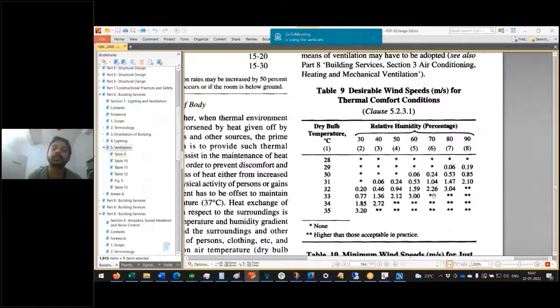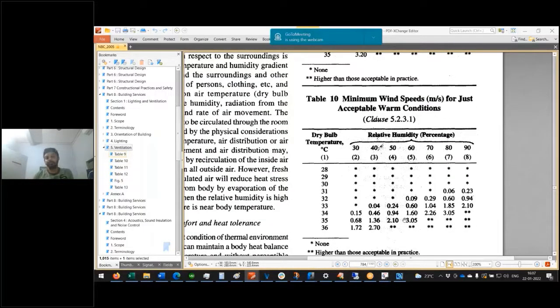You'll have to find out, with this velocity, let's say 3 meters per second, what is the area that you have for extraction. So you multiply the meter per second by the square meter, you will get meter cube per second. And how much the fan can extract. So you will have slots for the fan, so that is your area. From there, the velocity you want is 3 meters per second. So you will get exactly the quantity of air that can be removed. I hope you are understanding.